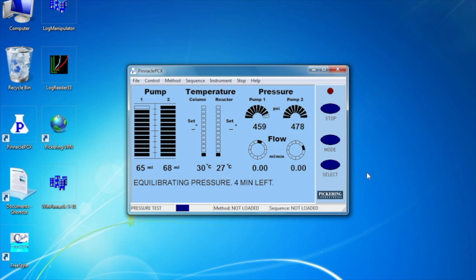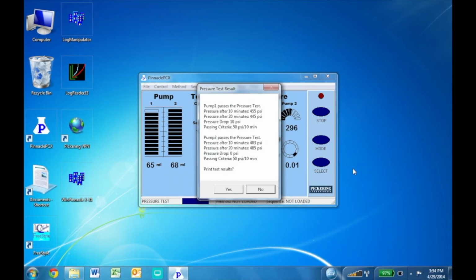Look for leaks by wiping a lint-free tissue by each nut on the valve, pump, and pressure transducer. Remove the waste lines from the waste bottle and look for any liquid coming out of the waste lines. If there is a small leak from one of the 5 small O-rings in the valve, it will leak out of port 6 to the waste. When the pressure test is done, you will have the option to print the results and then the pumps will empty to the waste.